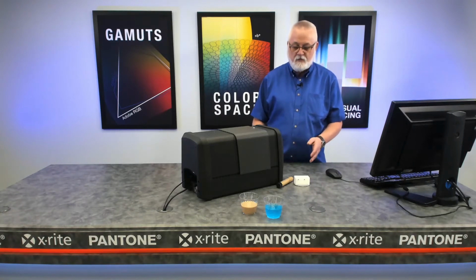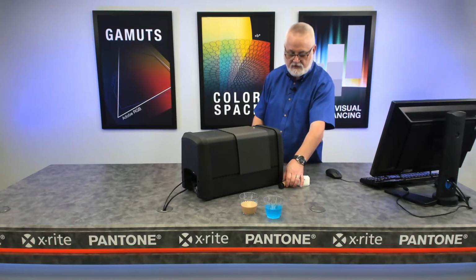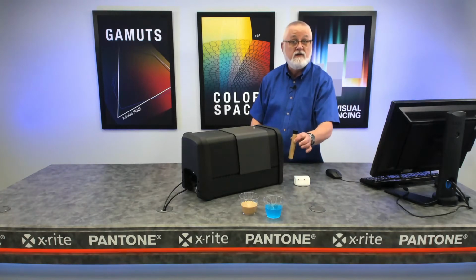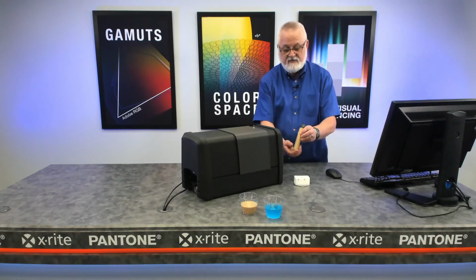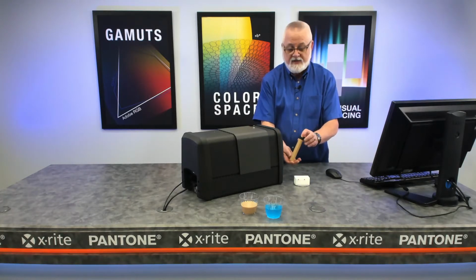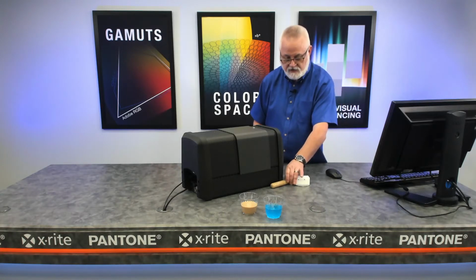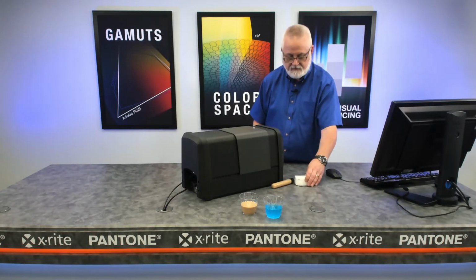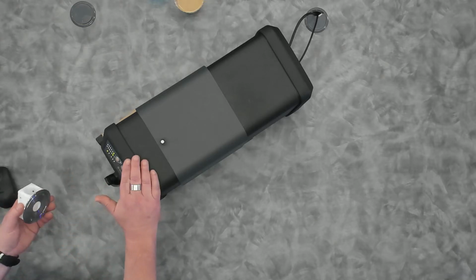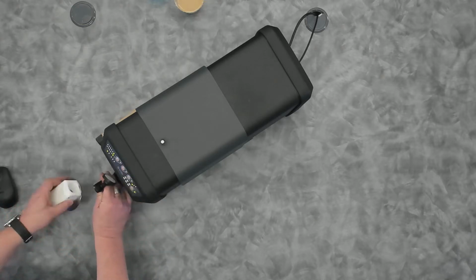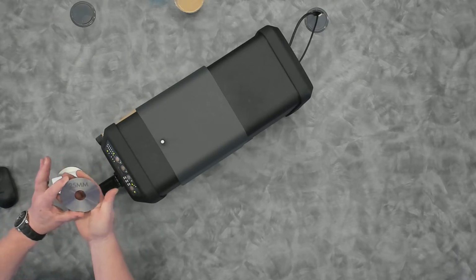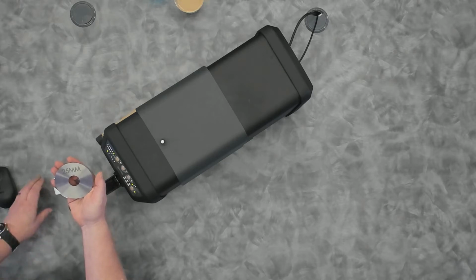We're going to start with this, which is creamed coffee, we'll call it, because that's kind of the color we've got that's in this tube. And in order to measure that, we're going to use this fixture. I'll lay the tube down for a second, which simply attaches to the front of the device. Now, I've calibrated my instrument using its 25 millimeter plate. Here's the 25 millimeter plate.